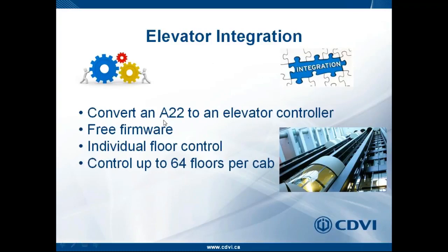I upgrade the A22's firmware to make it an elevator controller, and that allows that A22 elevator controller to communicate with the elevator controller itself with the relays. The elevator controller part number is the Centaur elevator controller, the CA480A. So that elevator controller controls 16 floors apiece. There are 16 relays. If I want to do 64 floors, I will need 4 of these elevator controllers communicating with one A22 EC to be able to control 64 floors.